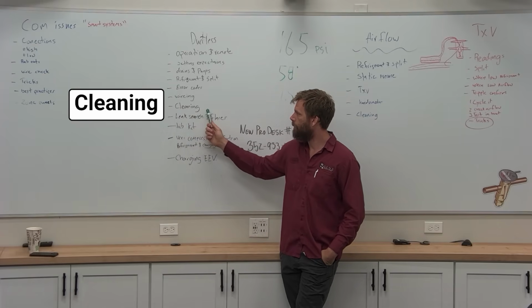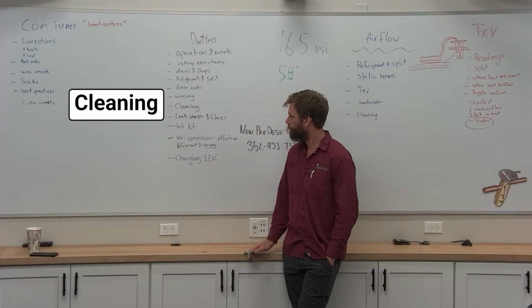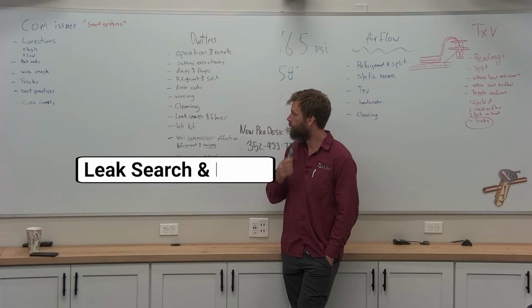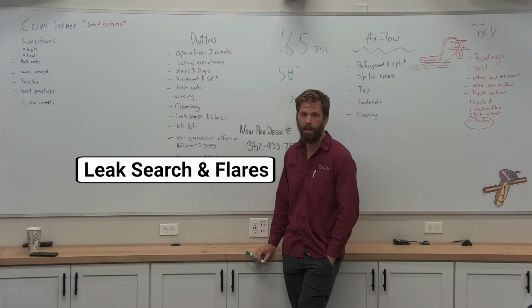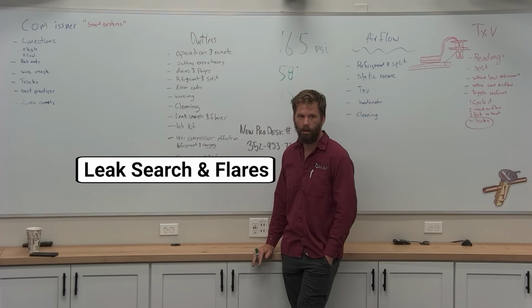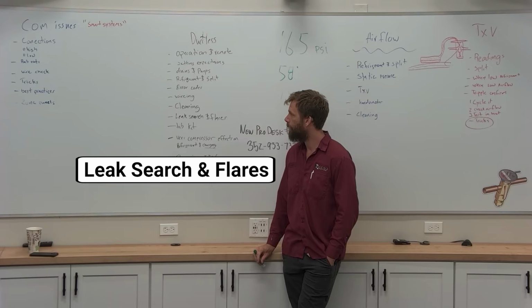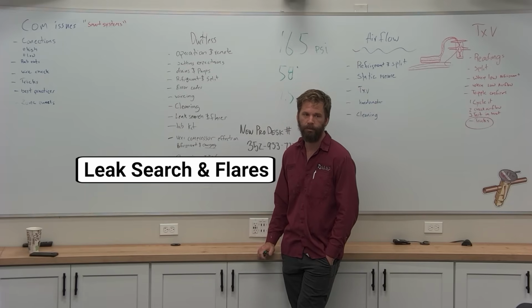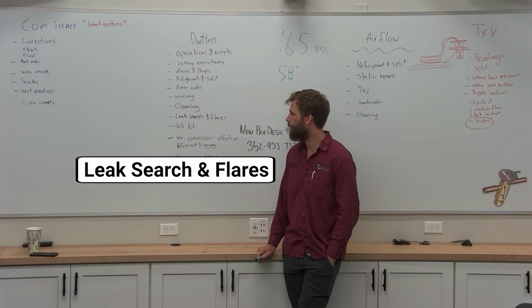Cleaning, check out the videos and get some reps. Don't be afraid of that. Leak search and flares. It is the most common place to be on the flares. Don't be just quoting an inside coil if you haven't checked also that inside flare joint. Let's make sure we catch all the leaks.